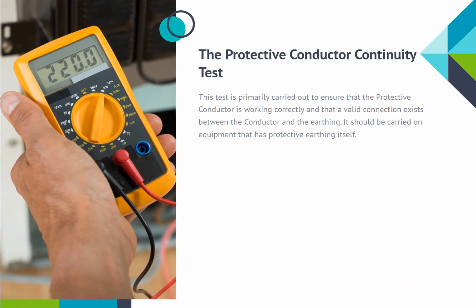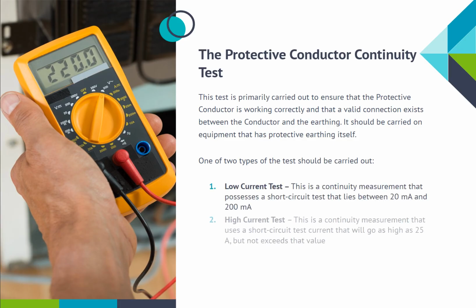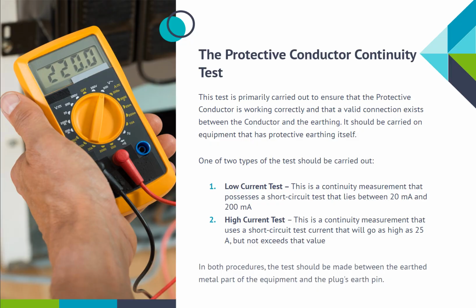The protective conductor continuity test. This test is primarily carried out to ensure that the protective conductor is working correctly and that a valid connection exists between the conductor and the earthing. It should be carried out on equipment that has protective earthing itself. One of two types of the test should be carried out.